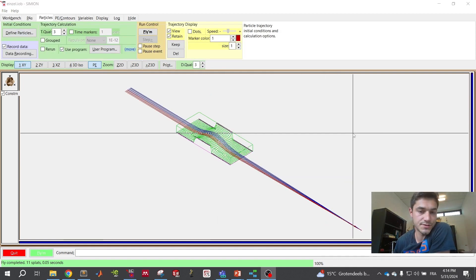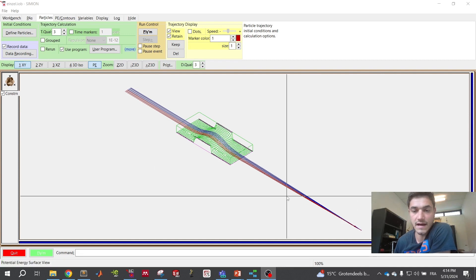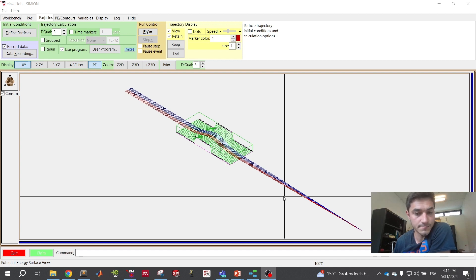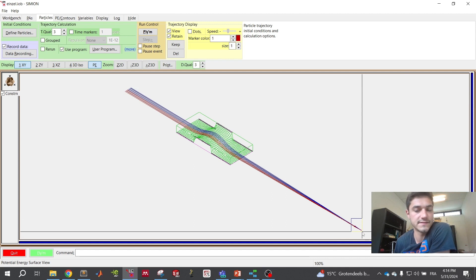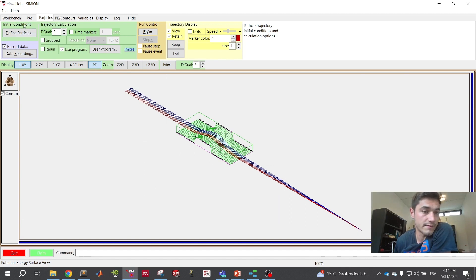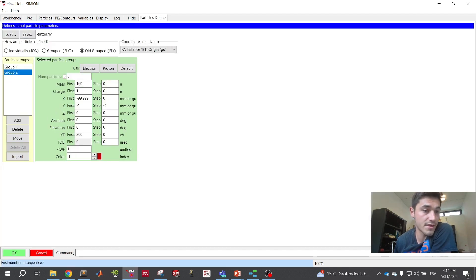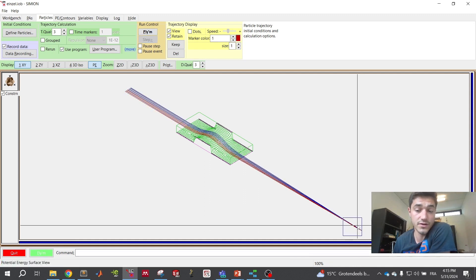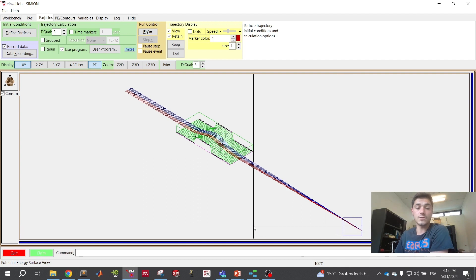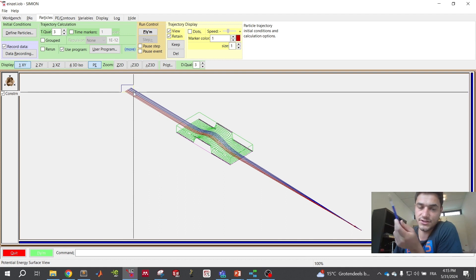An important question when simulating ions is: does mass have an impact? Imagine you have ions of different masses but want them all focused at the same point. Let's test this by setting the mass of group 2 to 300 instead of 100. When you fly the ions, you can see that all ions are still focused at the same point. This is because in an electrical field, if ions have the same kinetic energy, their trajectories are totally independent of mass.